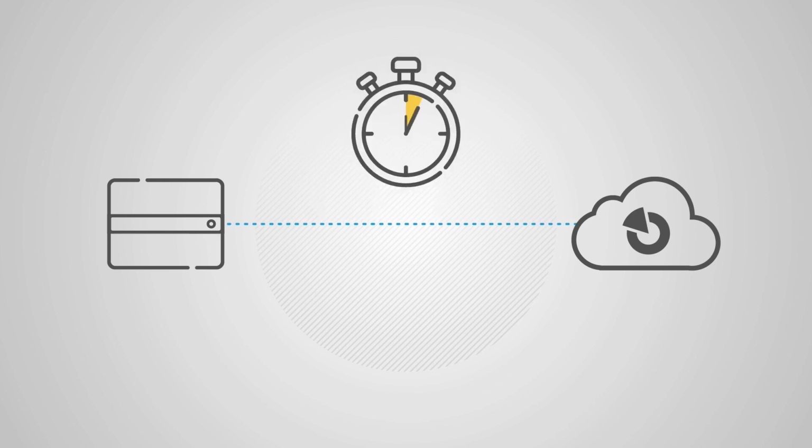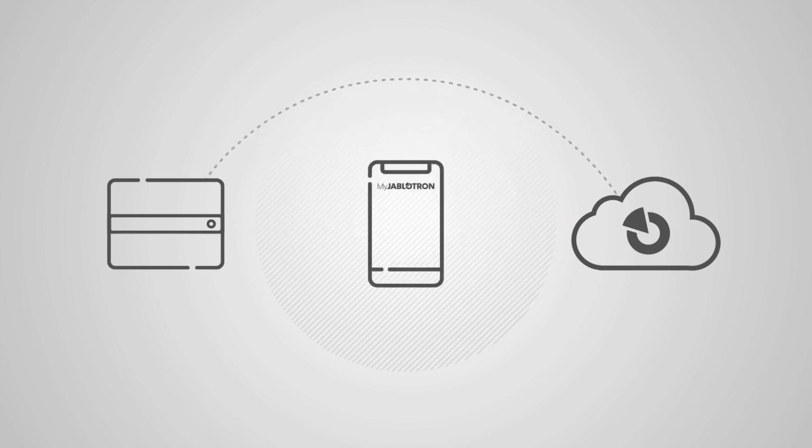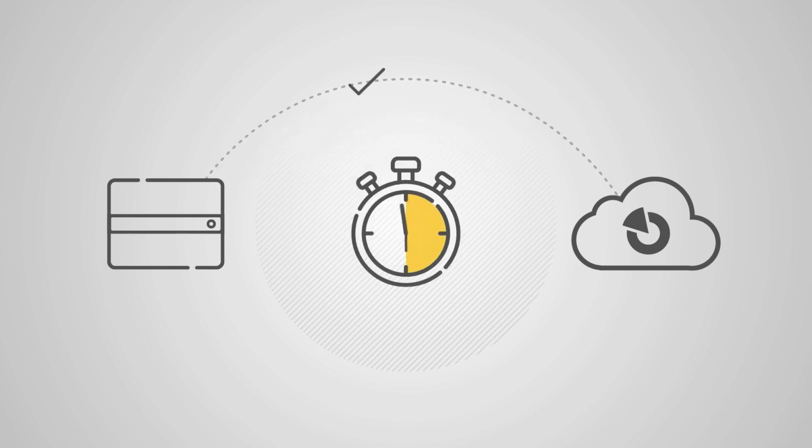There is supervisionary control every 15 minutes. It means that if there is no event in more than 15 minutes, a control event is created and sent to ensure that the channel is up and running. When Jablo SMS backup is used, there is only the event history in My Jablotron. Device control is not available, and supervision changes to a 6-hour schedule.